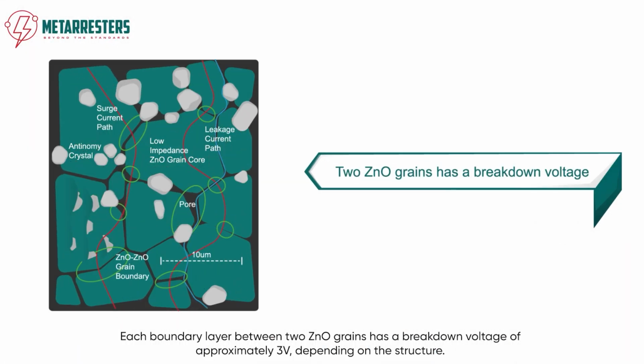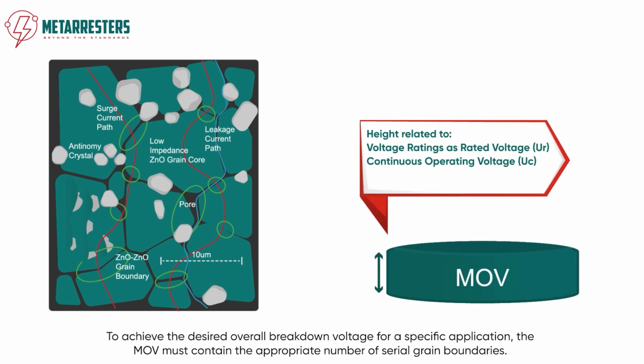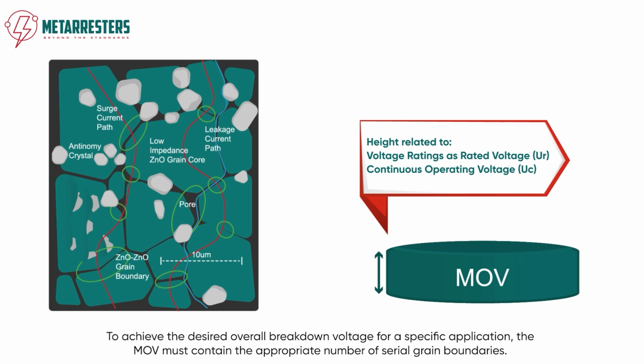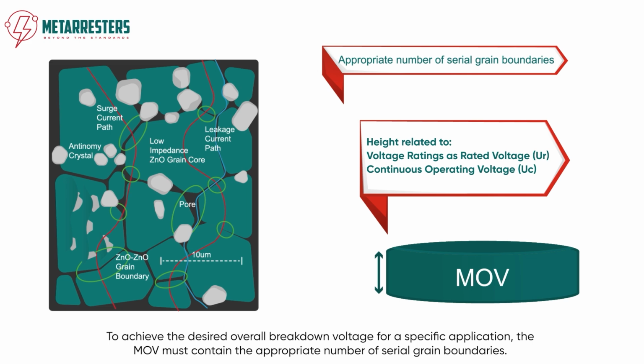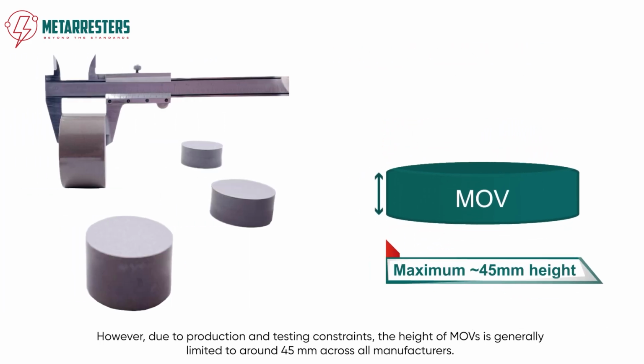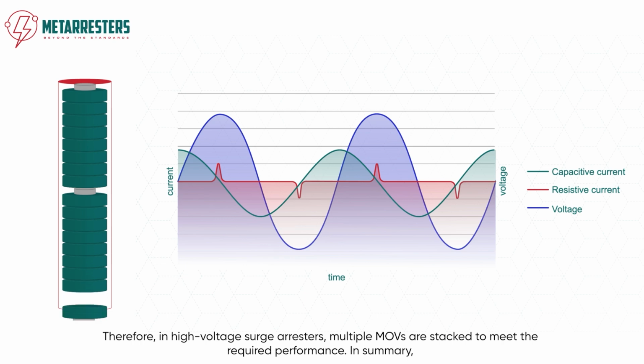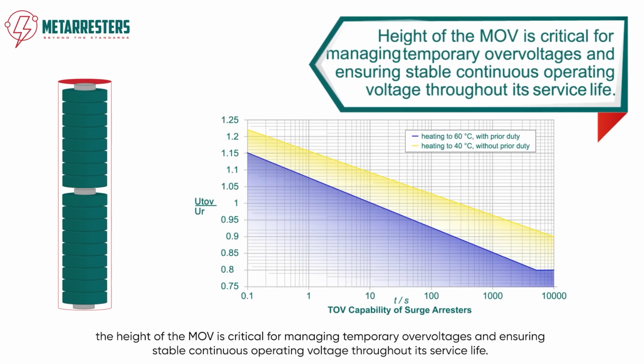Each boundary layer between two ZnO grains has a breakdown voltage of approximately 3 volts, depending on the structure. To achieve the desired overall breakdown voltage for a specific application, the MOV must contain the appropriate number of serial grain boundaries. However, due to production and testing constraints, the height of MOVs is generally limited to around 45 mm across all manufacturers. Therefore, in high voltage surge arresters, multiple MOVs are stacked to meet the required performance. In summary, the height of the MOV is critical for managing temporary overvoltages and ensuring stable continuous operating voltage throughout its service life.